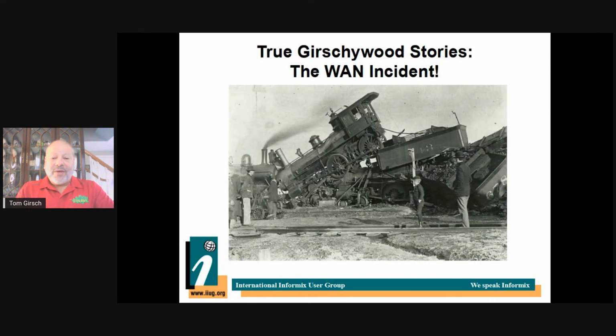Well, the WAN incident. We had an incident where our data center lost its connectivity to its primary WAN. No problem. We have redundant connections, redundant WANs with redundant power, except for whatever reason, the failover that the data center provider had in place didn't actually fail over. So we actually not only had a second switch, but a third switch, and third network. And we had to ultimately, while the data center figured out what was going on, manually fail our systems over to a third network provider.